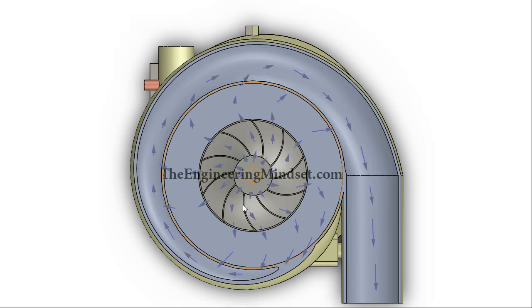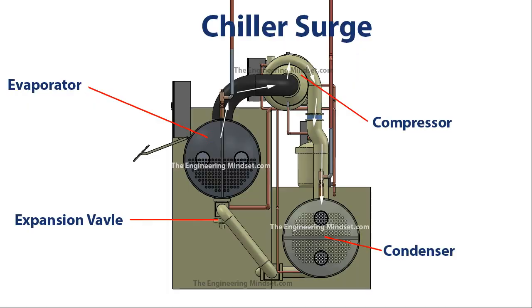This pressure builds up in the volute and forces the refrigerant out down through the discharge line into the condenser. It flows off of the impeller blades at all angles and builds up in this volute. In the section view, you can see the flow path from the evaporator through the suction line into the compressor, which is rotating and pushing that refrigerant out through the discharge line and into the condenser. The compressor causes a pressure difference across the impeller — the low pressure side is where it's sucking the refrigerant in, and the high pressure side is where it's pushing that refrigerant out, which collects and builds up in the condenser and discharge line.